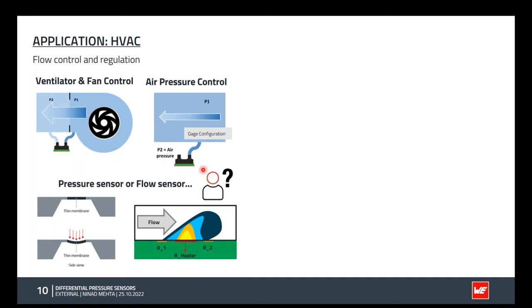So this also depends on your application, what kind of sensor you need to employ, because pressure sensor and flow sensor in the end are completely different. They work on completely different technologies. The pressure sensor we saw here works with the membrane. On the other hand, the flow sensors have a small heater, and the air passes through the heated element so that the air gets heated up. And then because of the heat dispersion inside the sensor, there are different air temperatures, and this can be measured electrically to determine what the flow of the system is.